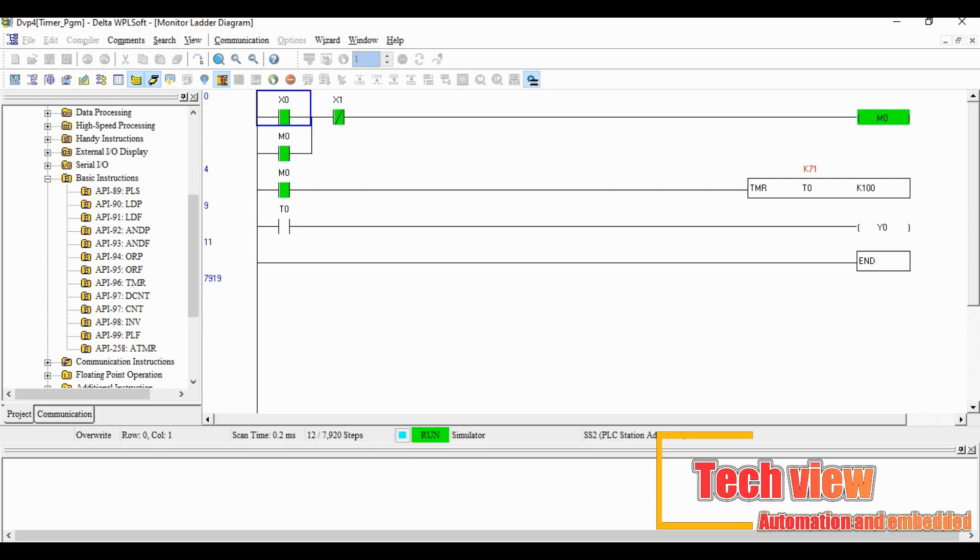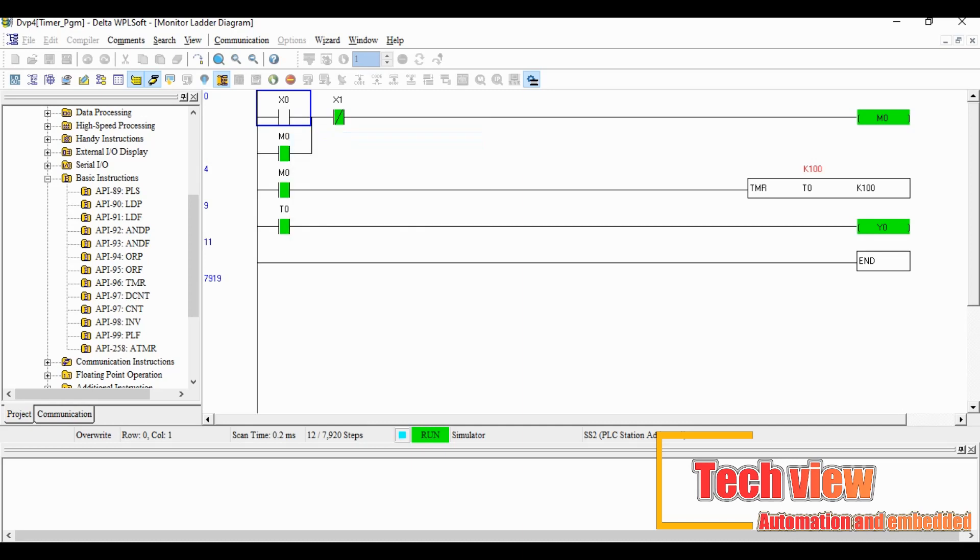Once the M0 closes, the timer starts to run, we can see it at the K. Once the timer K reaches the set point 100, the timer contact T0 enables and the output Y0 turns on.